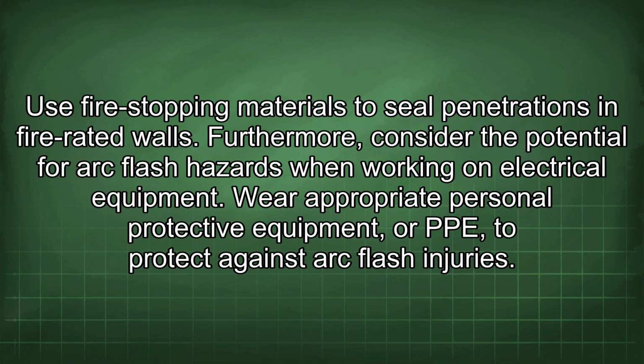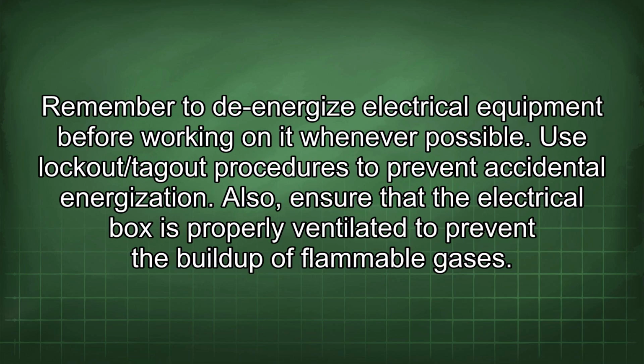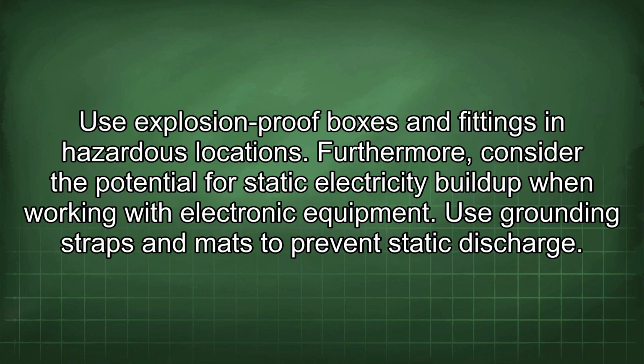Furthermore, consider the potential for arc flash hazards when working on electrical equipment. Wear appropriate personal protective equipment, or PPE, to protect against arc flash injuries. Remember to de-energize electrical equipment before working on it whenever possible. Use lockout/tagout procedures to prevent accidental energization. Also, ensure that the electrical box is properly ventilated to prevent the buildup of flammable gases. Use explosion-proof boxes and fittings in hazardous locations.